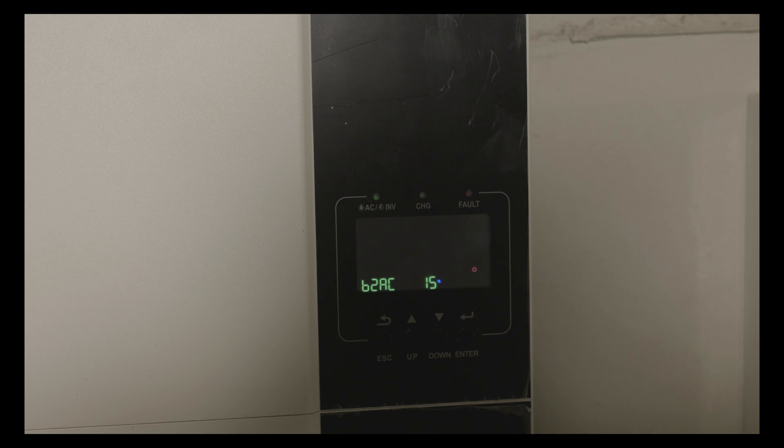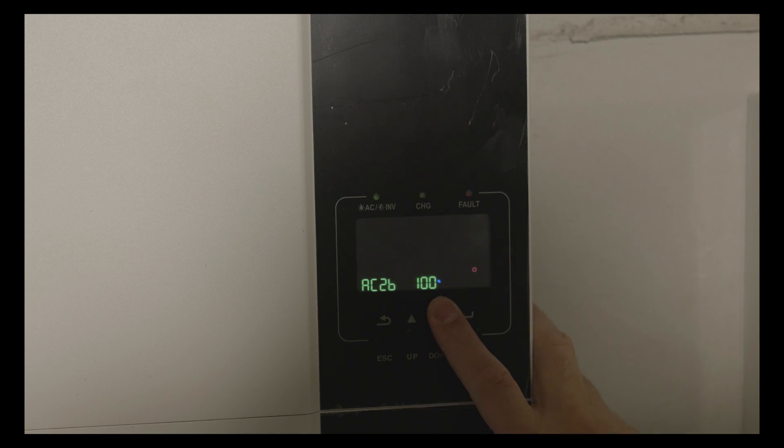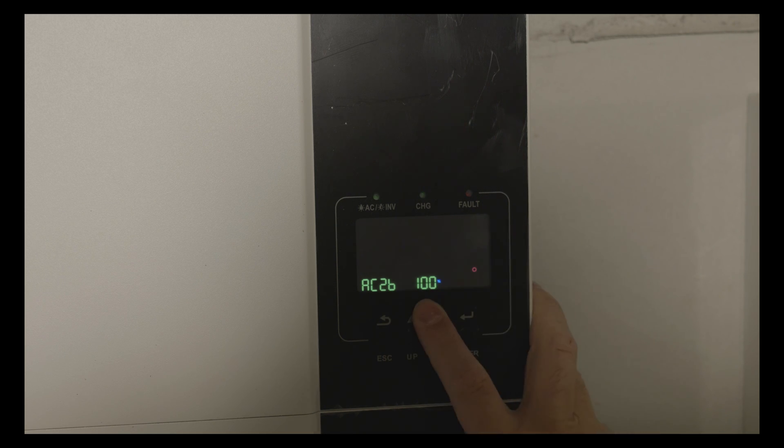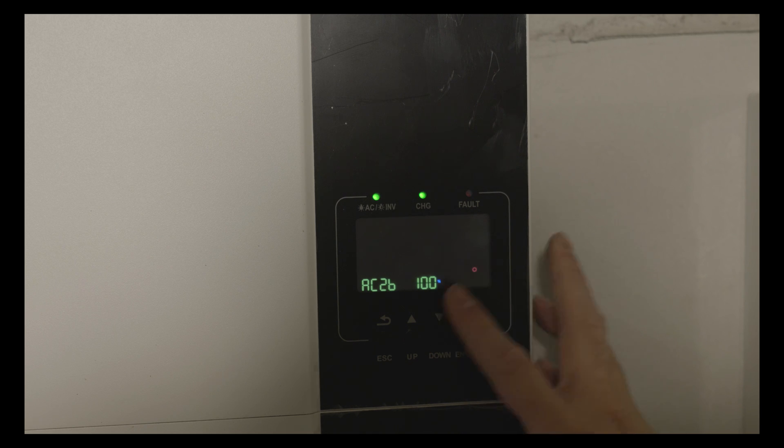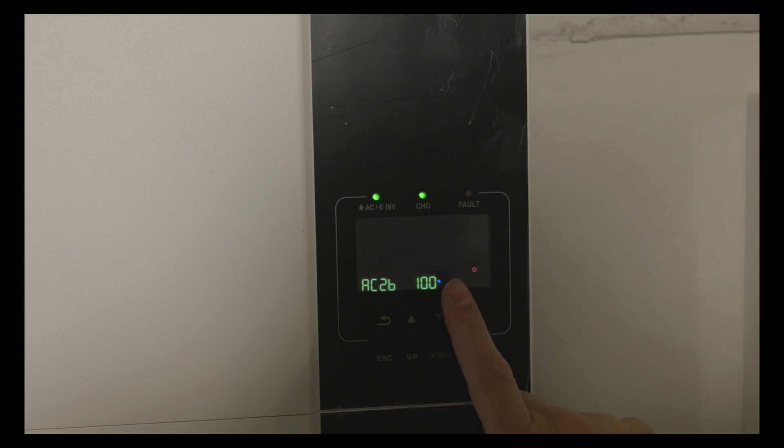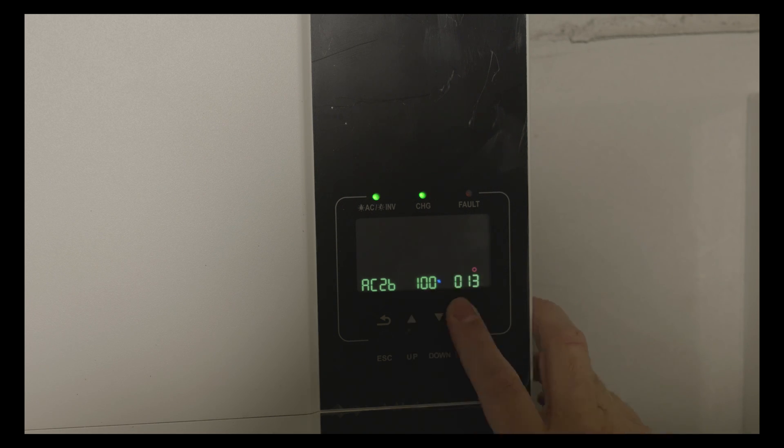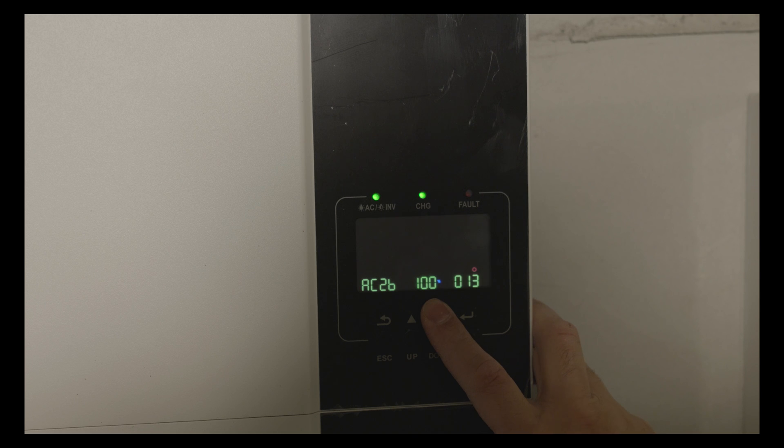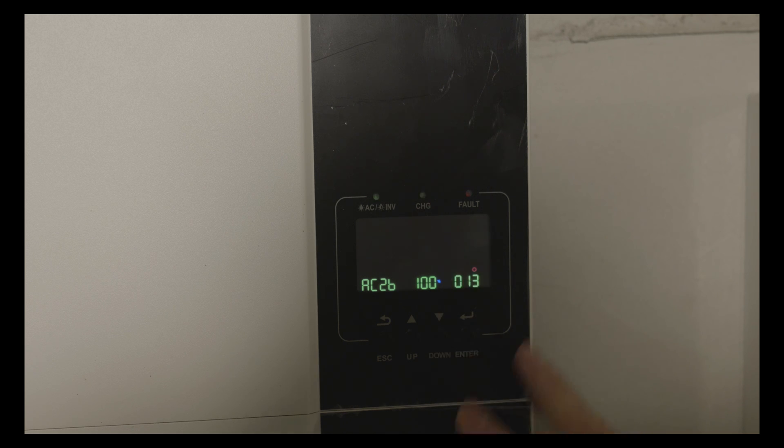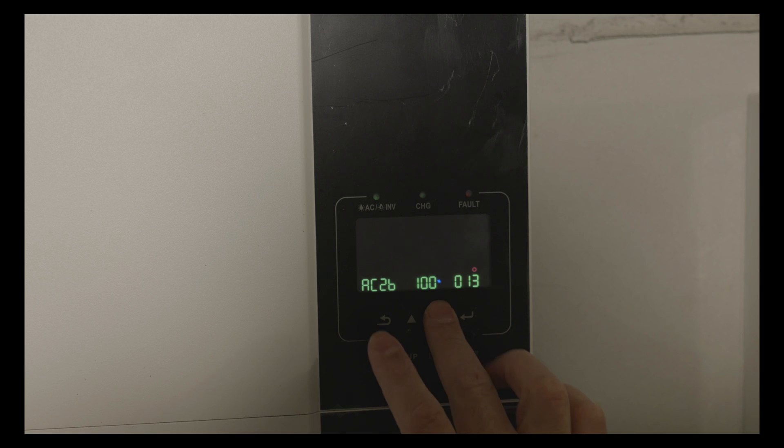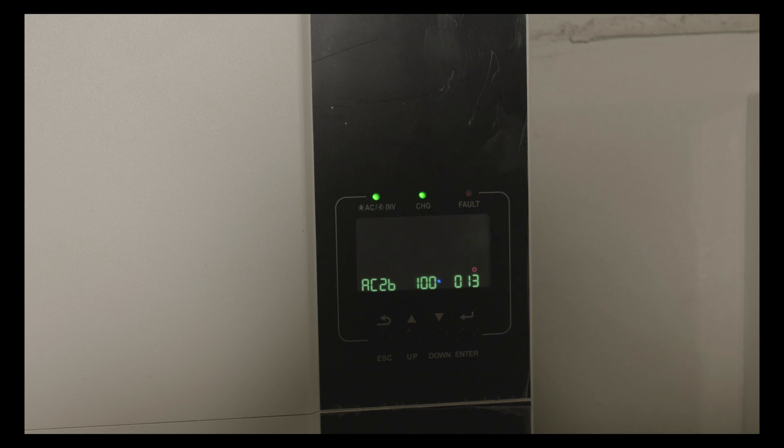The next option is AC back to battery. So when the batteries reach 100% in my case currently, it will switch to batteries again. This option will be in voltages if you are not using lithium option in battery type. I think my voltage here was 51, so when the batteries get to 51 volts it will switch to batteries. But again, trial and error and it depends on your batteries.